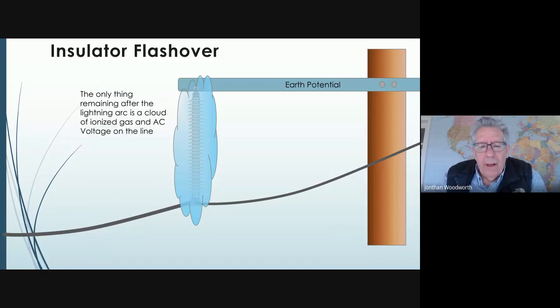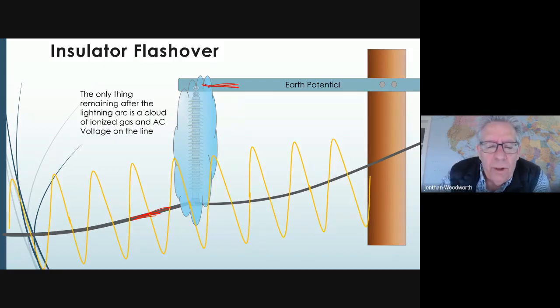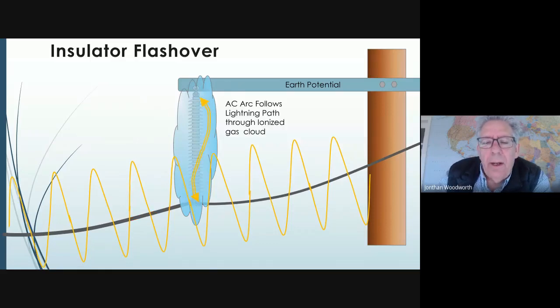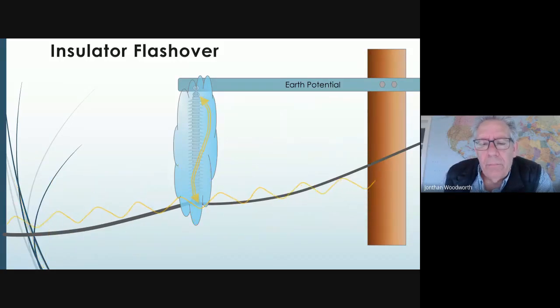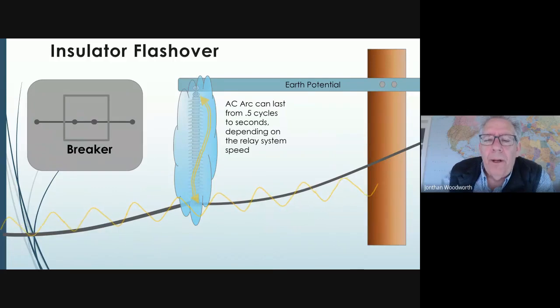So now we have a gas envelope that has very low impedance, and we have the power system here, and we have ground potential here. And when this AC voltage is there, which is there all the time, now we have the flashover, because this is a low impedance through here, and now the AC flashes over, and it stays flashed over until a breaker operates.